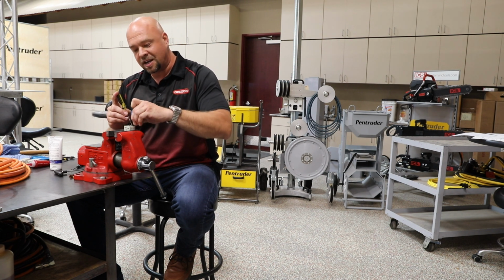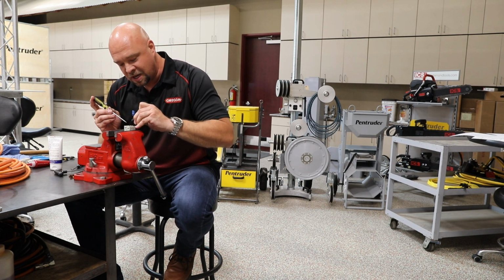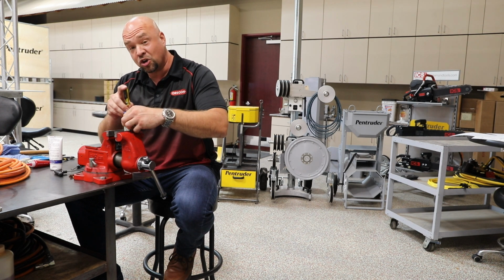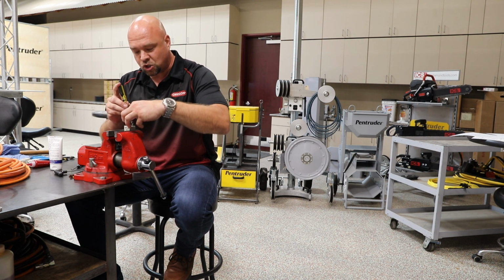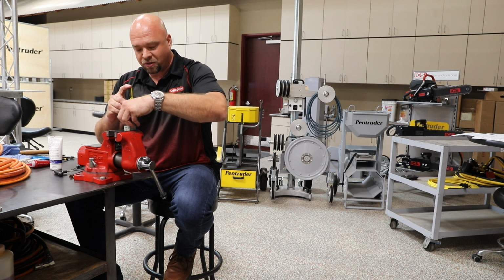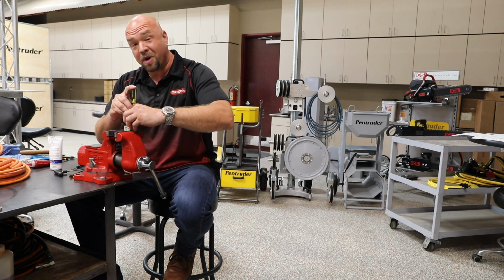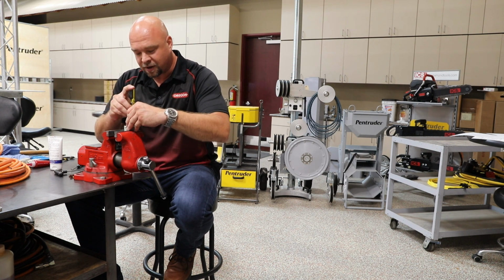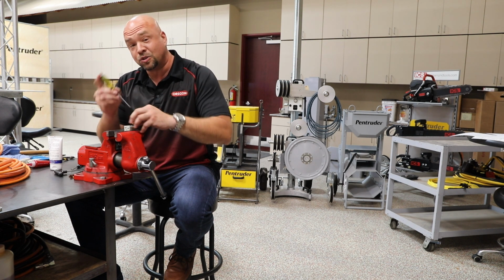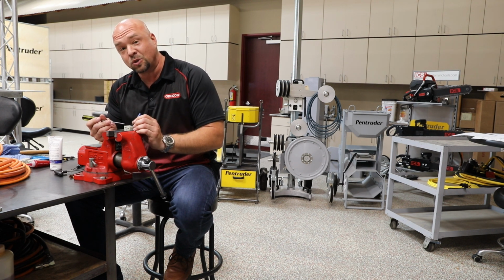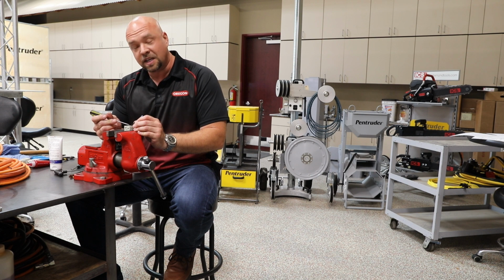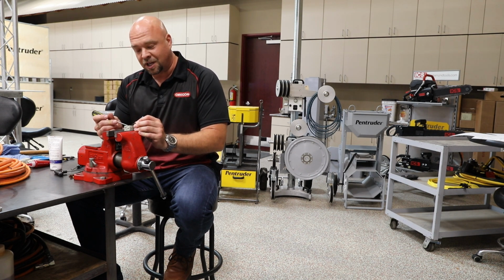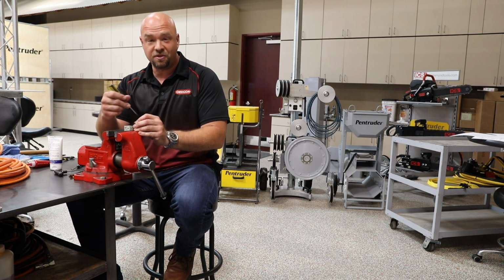Every time I replace a connector, I make sure, both visually and by pulling on it, that I have a good, solid, positive connection in those jaws. It's very important that the wires are all the way down, seated in the bottom of the connector. There's no wires exposed, and everything goes back in the corresponding place. After I replace the wire in the new connectors, I'm going to fill these holes with dielectric grease before I reassemble.